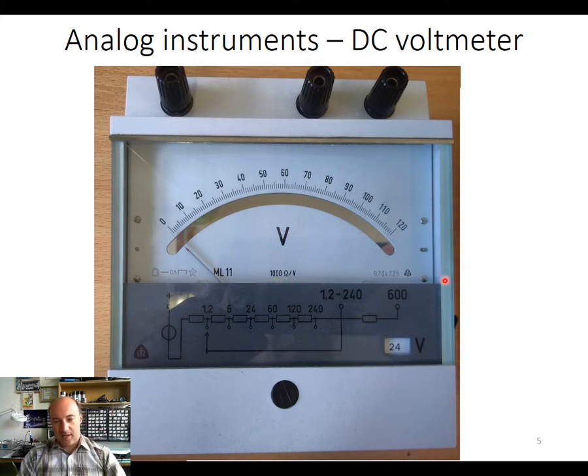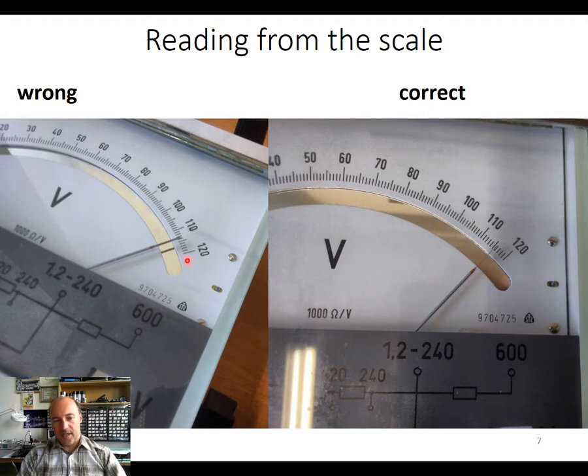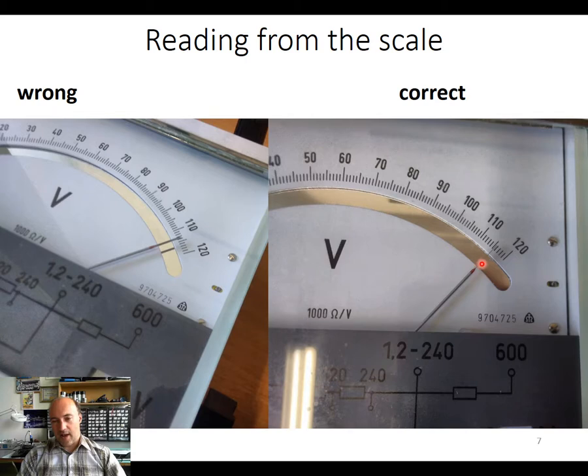It is very important to know how to read correctly from the scale. All instruments have a mirror behind the scale, and if you want to read correctly you need to position yourself so that the needle and its reflection in the mirror are aligned — you just see one line. Here is an example of how to read it correctly: this would be 115.5 divisions.